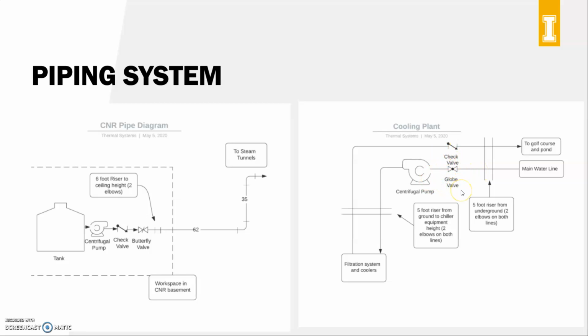And this globe valve is important because it allows you to control the flow coming in from the main water line. And the reason we need this is we need to have variable flow, because the cooling plant is not going to be taking the same amount of water all the time, and in the wintertime it might not be taking any water. And so we need a globe valve to allow us to vary the flow coming in from the main water line. Next, it'll go through a centrifugal pump, and I'll talk about this pump as well later. And it'll flow through and go into another set of risers.